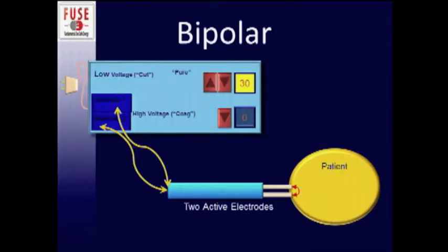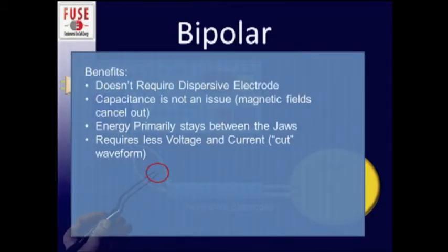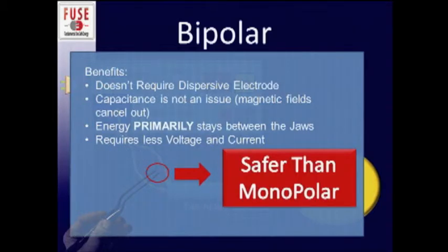With bipolar energy it's very different. In one end effector you have both electrodes, so the tissue coapted between the two electrodes is the only path where the electrons flow — they don't go through the patient in its entirety. This means you don't require the dispersive electrode. Capacitance, as Dr. Brunt covered, is not an issue because the two magnetic fields cancel one another out. The energy primarily stays between the jaws, requiring less voltage and current overall. Bipolar energy, by and large, is safer than monopolar energy.